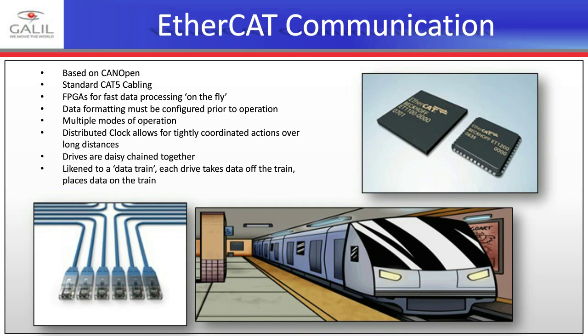EtherCAT communication is based on CANopen. For the purposes of this webinar, we'll be focusing on CANopen over EtherCAT, or CoE, which is an automation network protocol. CoE uses standard CAT5 cabling and Ethernet network interface cards, and features high-bandwidth communication up to 100 megabits per second. Minimal latency is achieved through hardware processing — instead of a microcontroller or PC interpreting data, dedicated FPGAs or CPLDs take the data from the EtherCAT packet and map it directly. There's no software sitting somewhere interpreting, addressing, unpacking, and repacking data — it's all done in hardware.